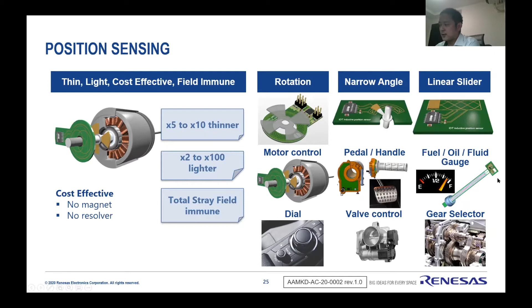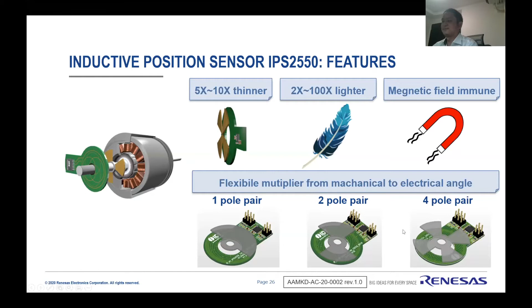Another benefit of this position sensor is its flexible multiplier from mechanical angle to electrical angle. If your motor is one pole pair, you can design the disc like this; if it rotates once, the electrical angle rotates 360 degrees. If your motor is two pole pairs, you design the disc differently, and if it rotates once, the position sensor outputs 720 degrees. Even if your motor is 4 pole pairs, it works the same way: if the motor rotates once, the position sensor can detect the corresponding change in angle.